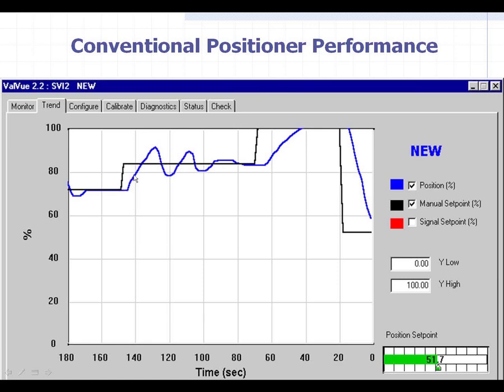You can see what the valve did: first there was a delay, and then when it went up it way overshot the set point and sat there and oscillated for a while. And then finally it may have gotten back down to the line, but many times it won't even get to the line.